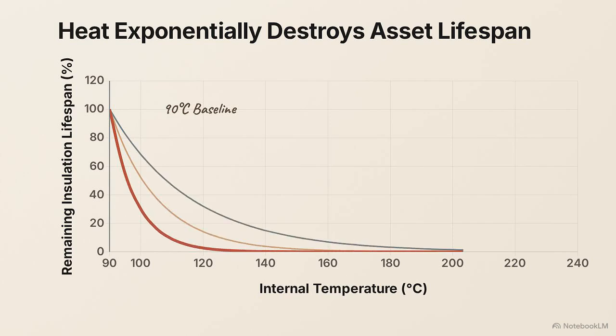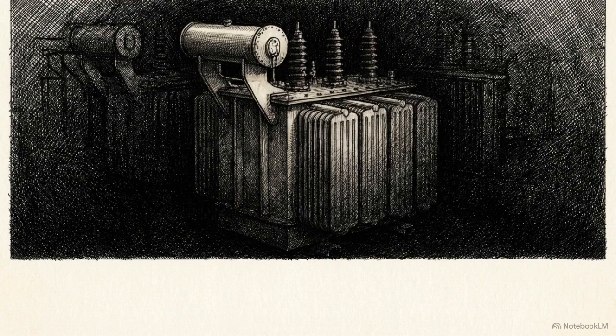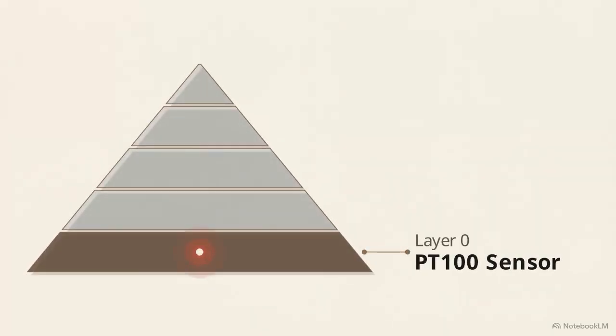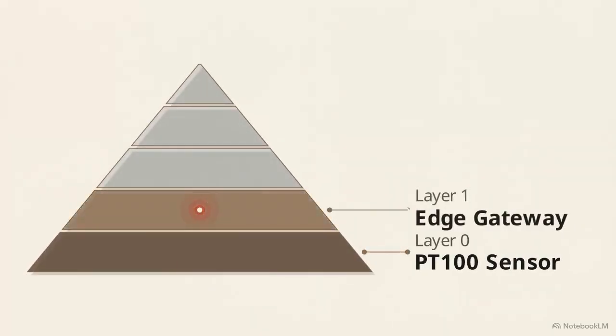This line graph plots internal temperature against expected asset lifespan. As the temperature pushes past 90 degrees Celsius, the curves drop sharply. Even a sustained increase of a few degrees exponentially degrades the remaining life of the insulation. Without extracting this instantaneous thermal data at layer 0, calculating an accurate predictive assessment of the transformer's health is mathematically impossible. The raw data from the PT100 sensor travels to layer 1, the edge gateway.